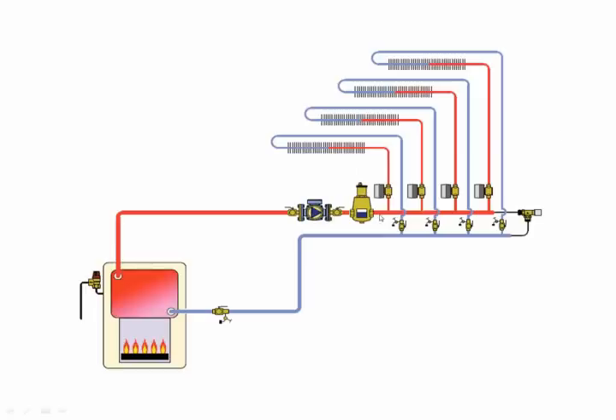Well, we know that where the temperature is hottest is where these are most effective, and coming off your boiler before you start sending it to your zones, that's hot. But is that the best place? Nope, because it's also the highest pressure. In front of a pump is always the highest pressure point in the system, and behind the pump is always the lowest pressure point in the system, okay? Pumps create head, everything else steals head. So a better place to put our air separator to work most optimally is where the temperature is highest and the pressure is lowest. Now we've optimized that air separator, okay?